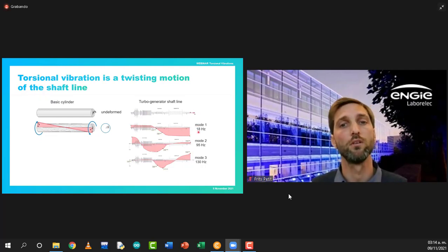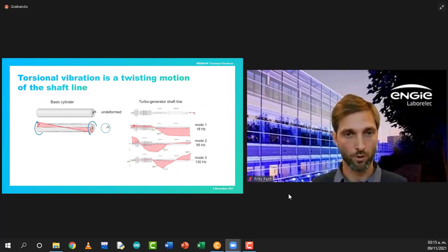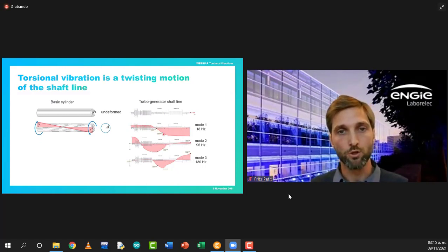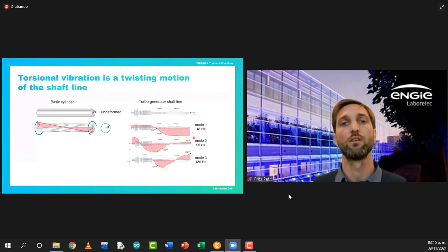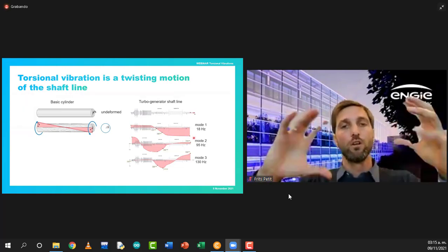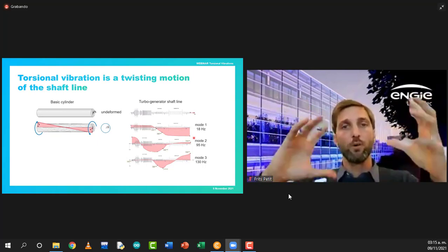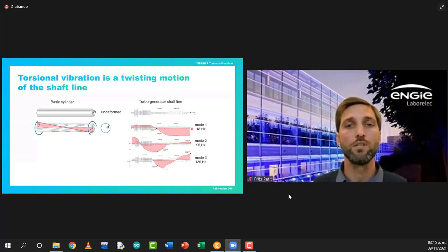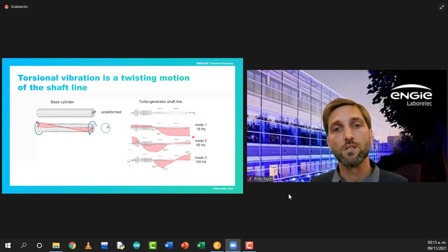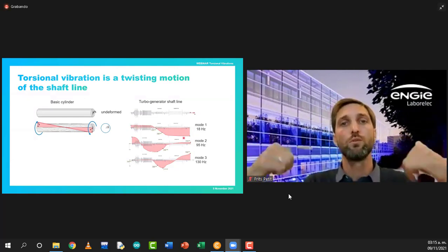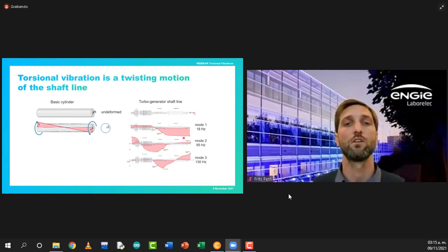You have multiple natural frequencies, torsional vibration frequencies. For instance, you can see here the lowest one at 18 Hertz, and this is the first mode. In that mode, the gas turbine behaves more or less as a rigid body and will be twisting against the generator. So you'll have a twisting motion of the gas turbine with respect to the generator at a frequency of 18 Hertz. This deformation is superimposed on a normal steady state rotation at 3000 or 3600 RPM.